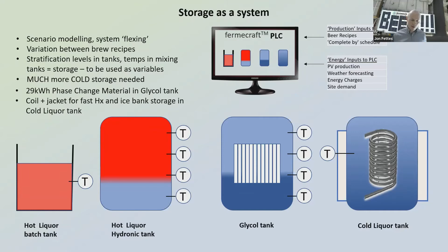Then we wanted to add more storage. We put in a 29 kilowatt hour phase change material thermal battery, which more than doubled the effective size of the storage in the glycol tank, and we added a large stainless steel coil in the CLT. The coil makes the system cool liquor much faster for multiple brew days, and it adds the possibility of ice bank storage for some operating scenarios. We can pull the temperature right down, and once it's at 0 we can keep adding cool into that if we want to keep heating out the other end, or do multiple batches rapidly.